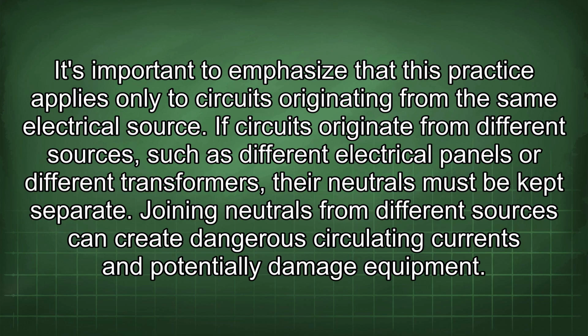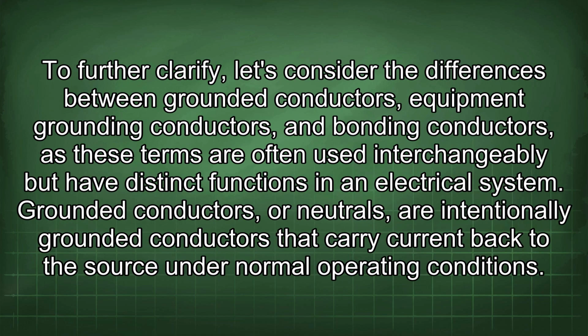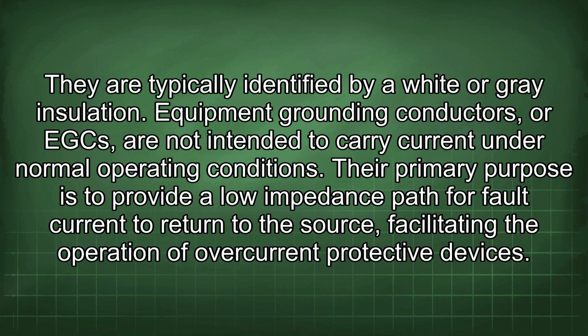It's important to emphasize that this practice applies only to circuits originating from the same electrical source. If circuits originate from different sources, such as different electrical panels or different transformers, the neutrals must be kept separate. Joining neutrals from different sources can create dangerous circulating currents and potentially damage equipment. To further clarify, let's consider the differences between grounded conductors, equipment grounding conductors, and bonding conductors, as these terms are often used interchangeably but have distinct functions in an electrical system. Grounded conductors, or neutrals, are intentionally grounded conductors that carry current back to the source under normal operating conditions. They are typically identified by white or gray insulation.